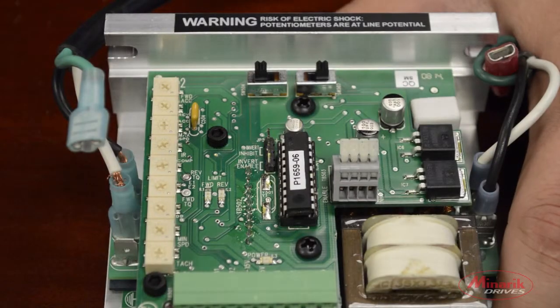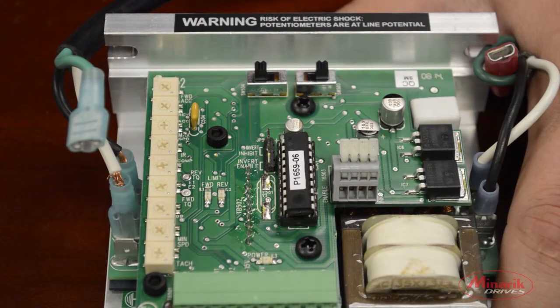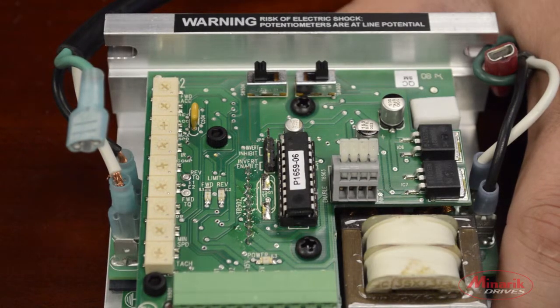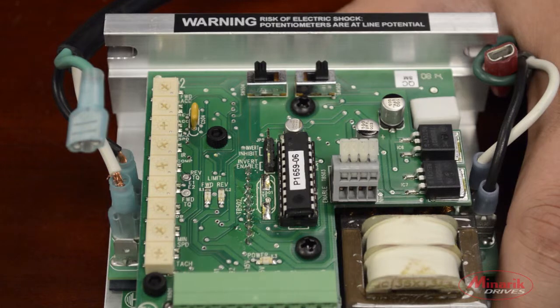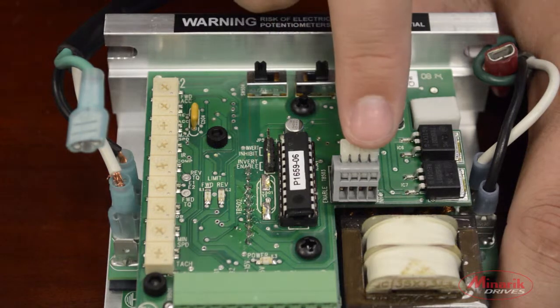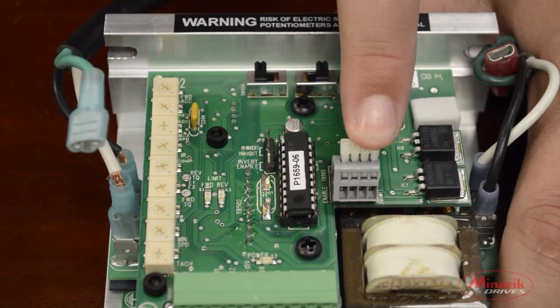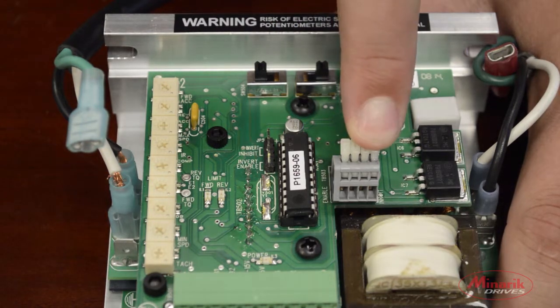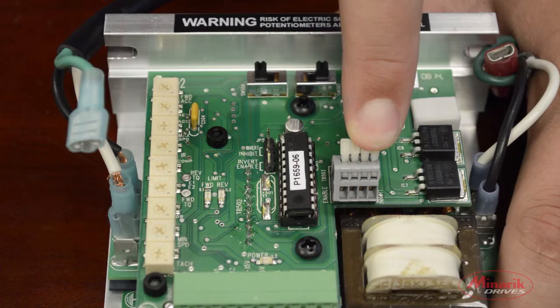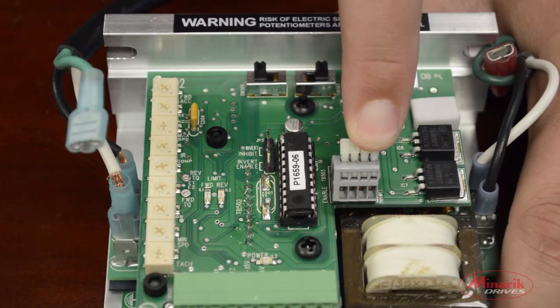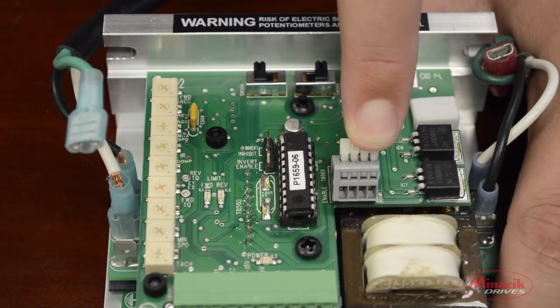Next, we'll go over the different inhibit settings and enable settings. Factory default states that when the two inhibit terminals located here are closed, the drive will activate inhibit.